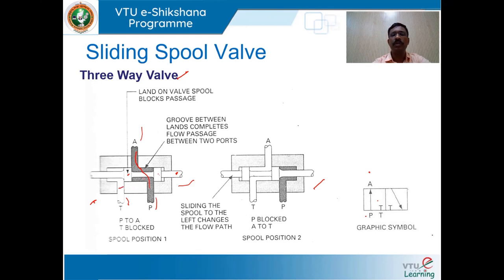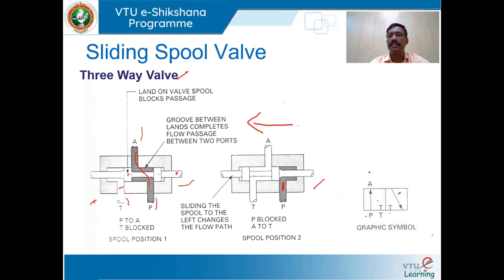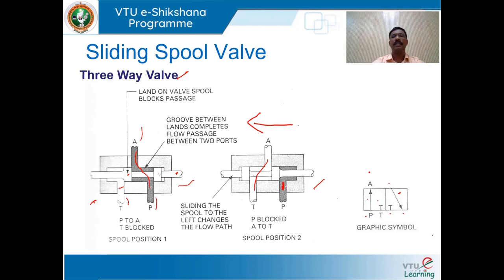When the spool slides within the valve body and moves to the second position — denoted by another adjacent square — P is blocked with no connectivity between P and A, and A is connected to T. There are two switching positions, and port opening and closing occurs as the spool slides within the valve body.